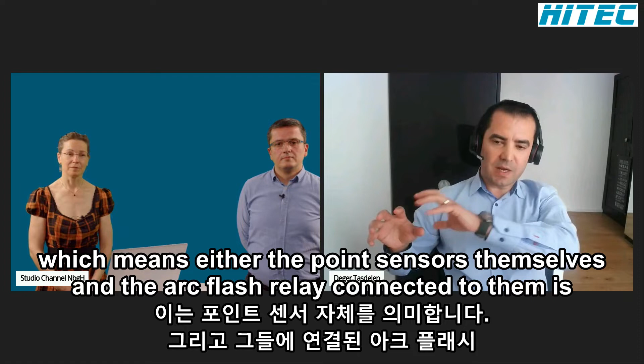In addition, this may also answer many of the questions I see on the flow. The SIQuench system has a self-monitoring feature, meaning the point sensors themselves and the arc flash relay connected to them are self-monitored. Additionally, the SIQuench on top of the bus bar with the SIQuench controller is also self-monitored. In case of any problem, it tells you, hey, take care of me.